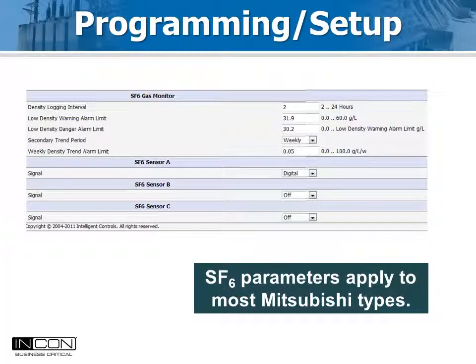This part of the screen sets up the SF6 density parameters. Here, the warning and lockout limits for SF6 gas are entered along with the sensor type. Digital true density sensors are standard with the Optimizer 2, but temperature compensated pressure sensors giving a 4 to 20 milliamp analog signal may also be used.